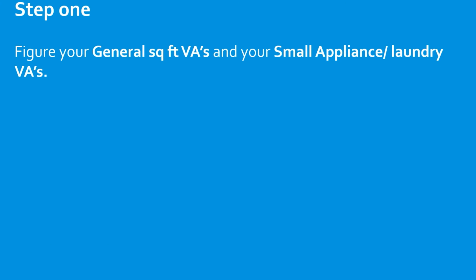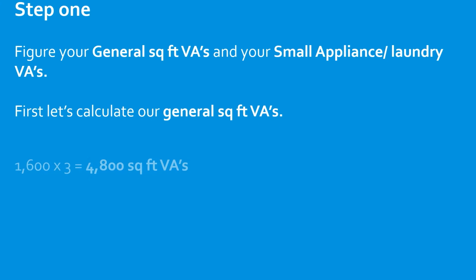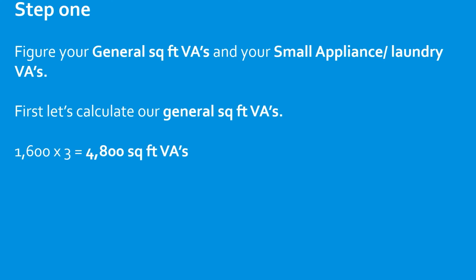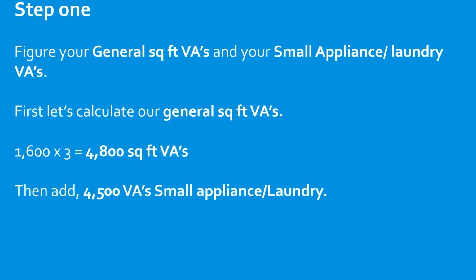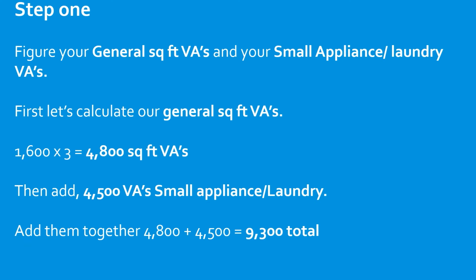Step 1, first you figure your square foot VAs and your small appliance laundry VAs. First, calculate your general square foot. In this case, we had 1,600 square foot per apartment. That multiplied by 3 VAs per square foot for dwelling units is going to give us 4,800 square foot VAs. Then just add the 4,500 small appliance laundry circuit VAs. Add them together. That's going to give us 9,300 total. We have 9 units, so we are going to multiply 9,300 by 9, and that is going to give us 83,700 VAs.